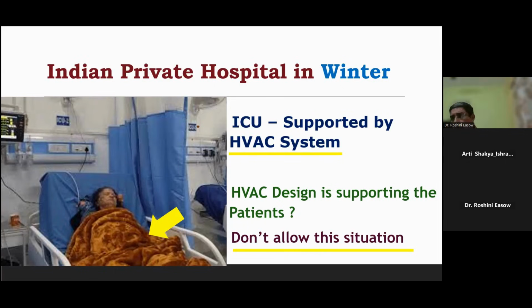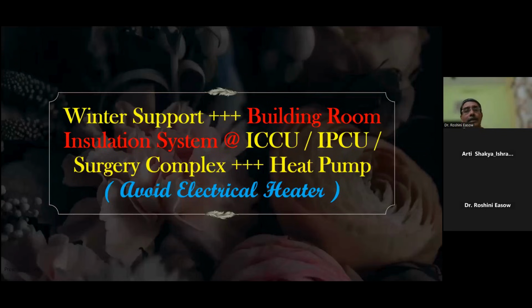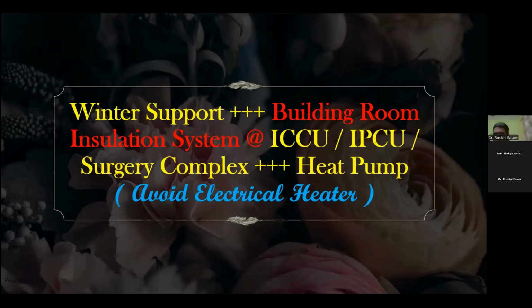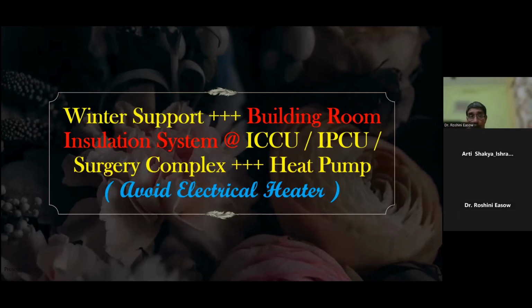And another thing I'm telling you is do not use electrical heaters. I have also seen in North India ICU rooms, even in a surgery room, they are using a heater, because they don't have a heating system. They have a cooling system. Now, what problem may happen? In case of an electrical heater, your oxygen percentage will come down and carbon dioxide will go up. So it is not at all acceptable.